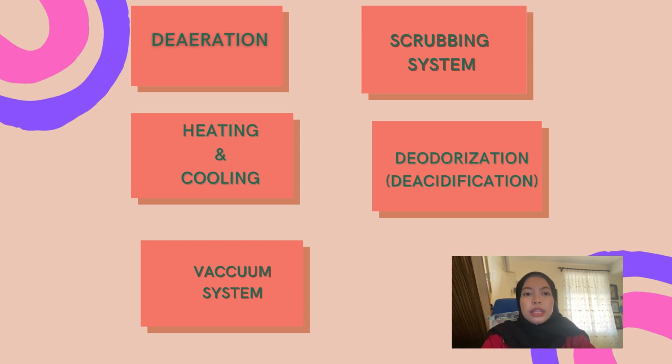And then the thermosiphon system is a special method of heat recovery that is used in semi-continuous deodorizers. Steam produced in the oil cooling section flows in a closed loop to the oil preheating section. It will condense, then the water flows back to the cooling section. In this way, a heat recovery of 45 to 75% can be achieved depending on the design of the thermosiphon system.